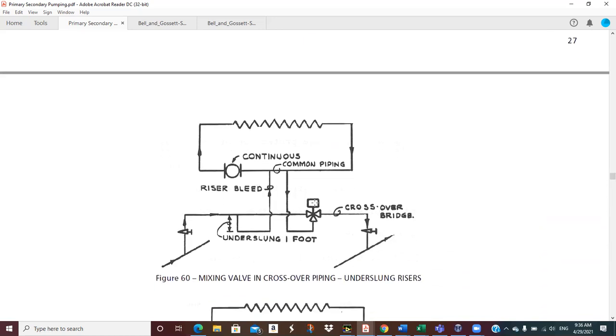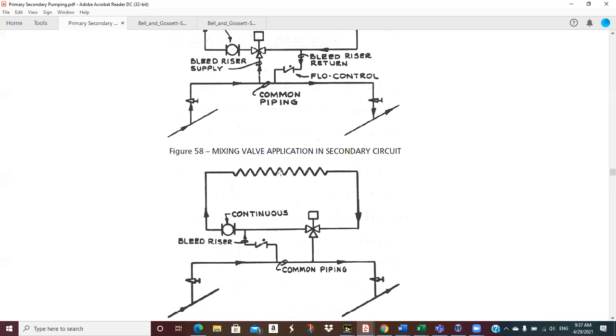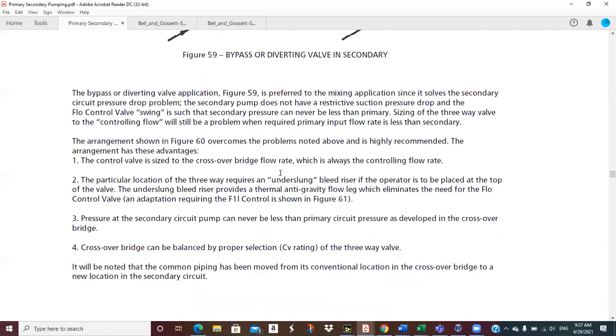And now we'll go back and read the comments. So it's kind of like the good, the ugly and the bad, and this is the good. It's in reverse order. So this is their recommended arrangement if you're going to use a three-way valve. And notice that we're showing the three-way valve down here in the crossover, and that makes the common pipe move up here as part of the secondary. Kind of interesting. And we'll see his comments in a second. If you look on these, then our common pipe is in the crossover bridge where we're kind of used to seeing it. Okay, let's look at the comments.